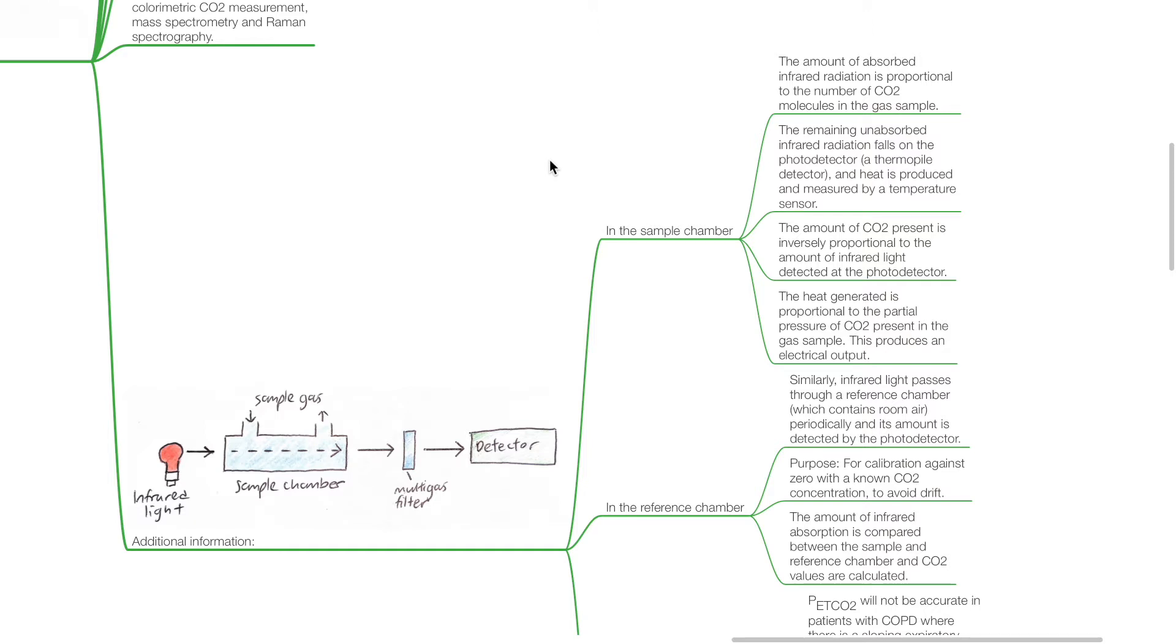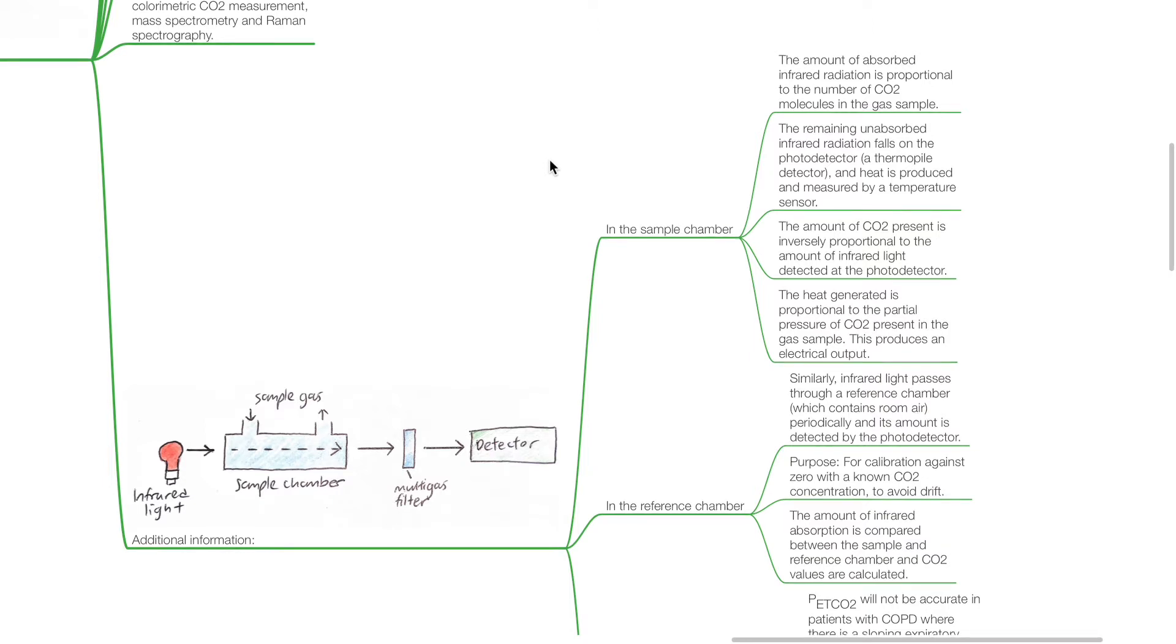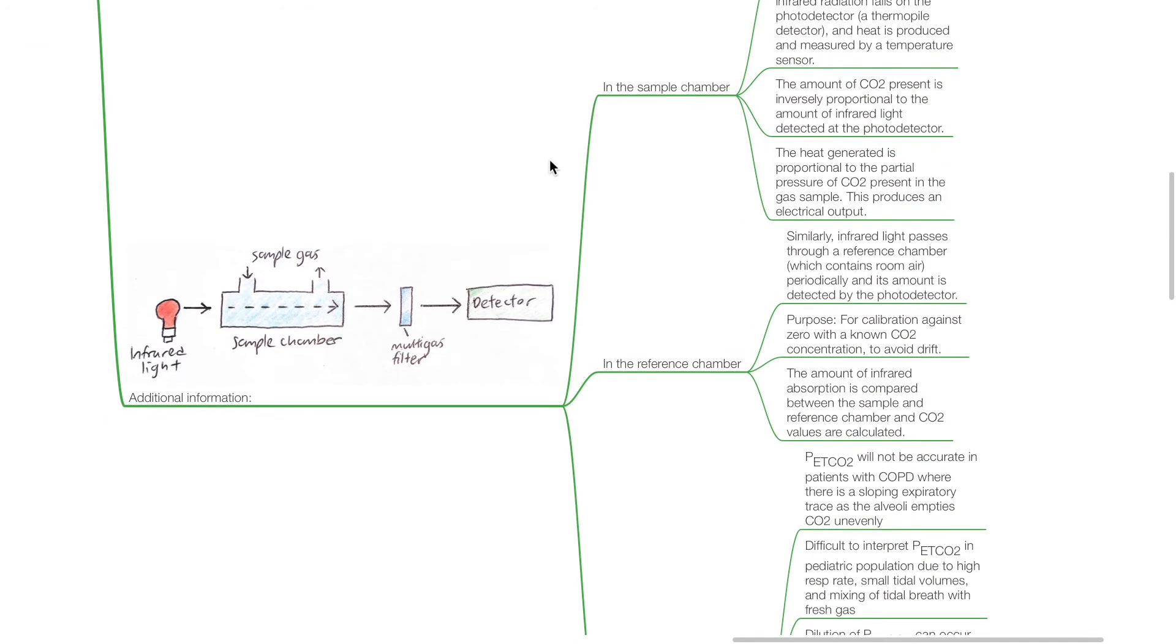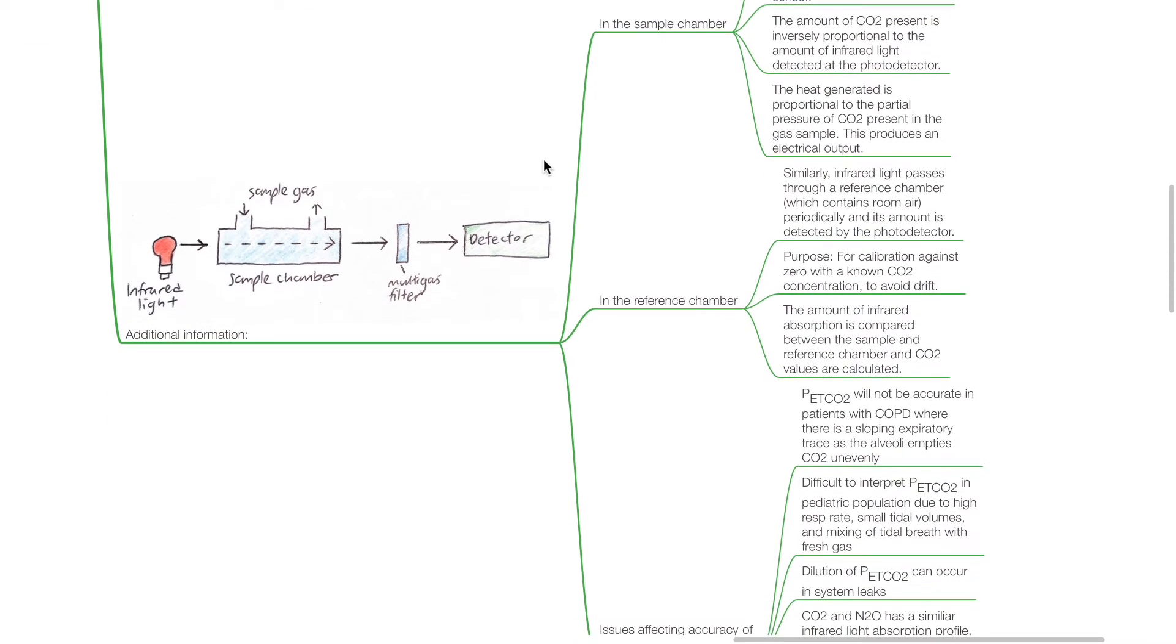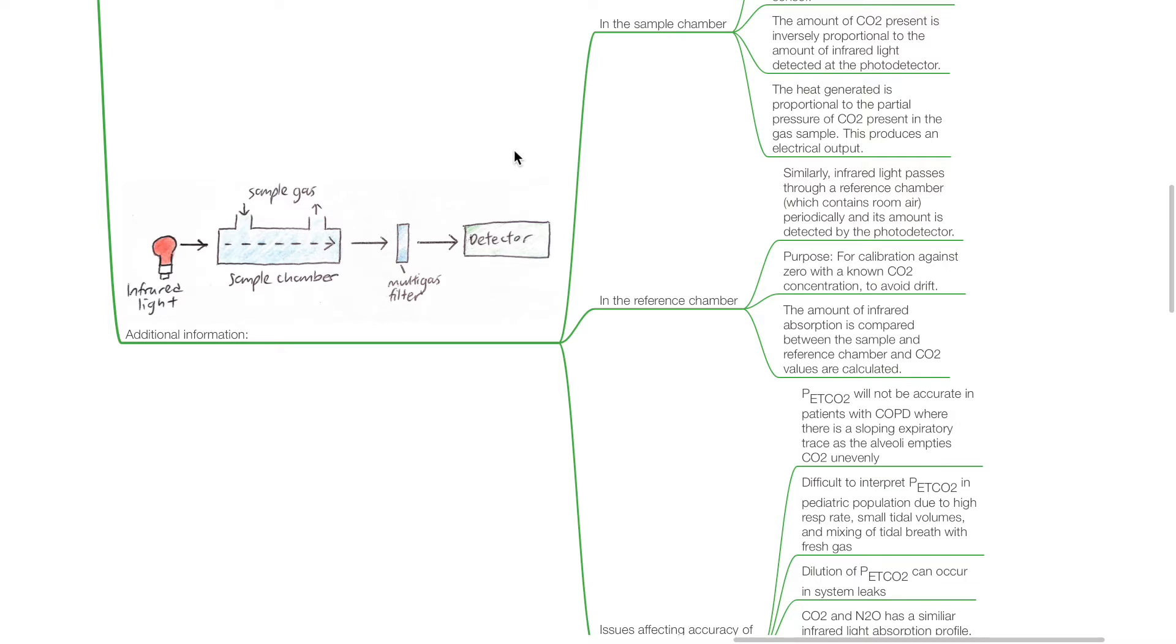The amount of CO2 present is inversely proportional to the amount of infrared light detected at the photodetector. The heat generated is proportional to the partial pressure of CO2 present in the gas sample. This produces an electrical output. In the reference chamber, infrared light passes through a reference chamber which contains room air periodically and its amount is detected by the photodetector. Its purpose is for calibration against zero with a known CO2 concentration to avoid drift. The amount of infrared absorption is compared between the sample and the reference chamber, and CO2 values are calculated.